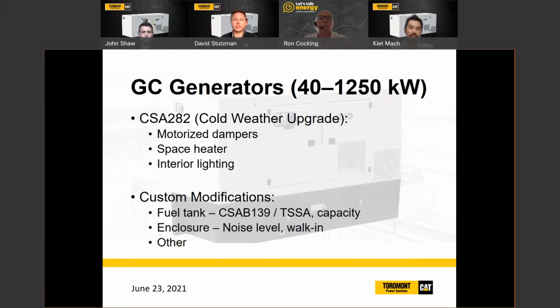I also wanted to share some of the regional requirements in Canada that we commonly see in upgrades and modifications we perform. The first is CSA 282, otherwise known as life safety or cold weather upgrade. We commonly add these to our packages if they're not available from Caterpillar. That entails adding motorized intake dampers and gravity discharge dampers to the air intakes and discharge, which helps seal up the unit to prevent wind or weather from entering the enclosure, keeping it warm.